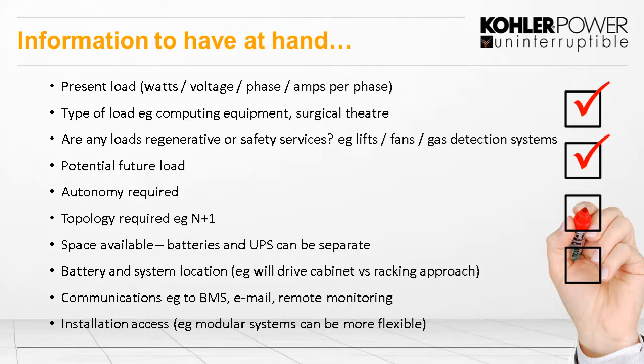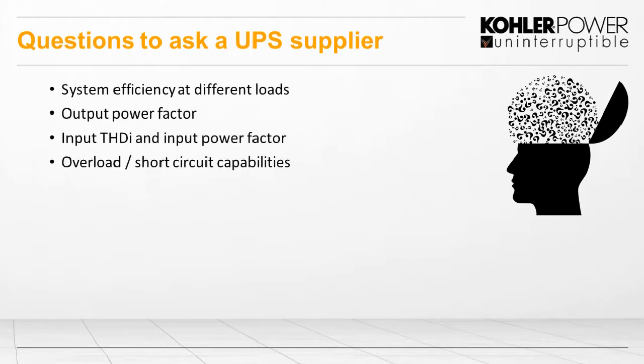So some of the things you might want to be asking from a UPS supplier is, what's the system efficiency of the UPS, and especially at different loads? Modern UPSs are very efficient, and typically they're great between 50 and 100%, but below that, what are they? And we need to be careful.